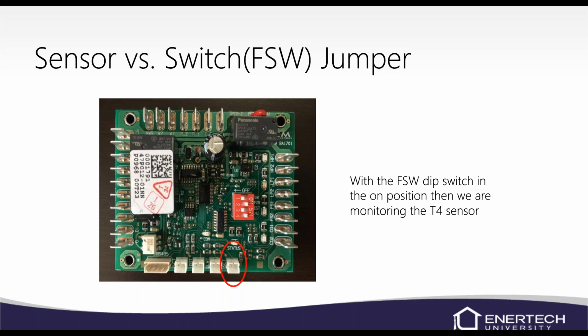So on dip switch number 1, if you get this unit from the factory and you have sensors plugged into these 4 on the bottom, then FSW, that first dip switch, will be in the on position, and we're going to be monitoring the T4 sensor, which is the one that's circled. That's your source coax temperature. On the newer units, we're not monitoring a flow switch. We're monitoring water temperature or thermistor temperature. It's not even water temperature, it's refrigerant temperature at the source heat exchanger.